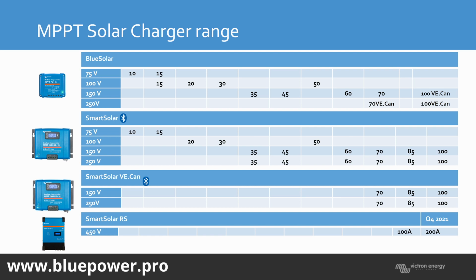Sorry, just a question for clarity. Is it only the RS that has got the multiple tracking on the MPPTs? Yes. And not the others? Yes. So only the new SmartSolar RS MPPTs have got the dual or quadruple trackers built in. Those are the newer units. They're also the bigger units, so they almost have this form factor with the fans for cooling built in. So the 450/100 has got 2 trackers, and the 450/200 has got 4 trackers.